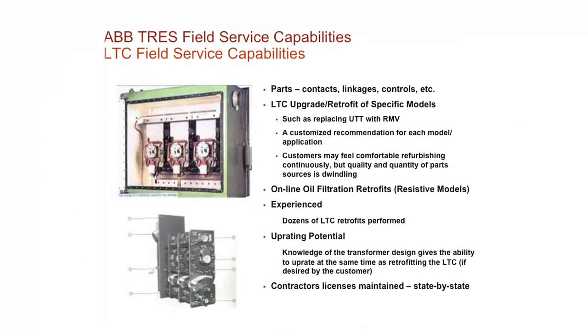Maintenance specific to what we call the arc-in-oil LTC compartment. Basically, you've got to thoroughly clean them. You're going to have carbon inside these compartments because of the arcing going on. So when you drain the oil, you're going to see it looks like a lot of black carbon has been in there. You need to clean all those thoroughly, clean the contacts thoroughly, clean your insulation boards thoroughly so you don't have any tracking, anything of that nature. And then again, pay attention to the mechanical wear and arcing of the contacts.